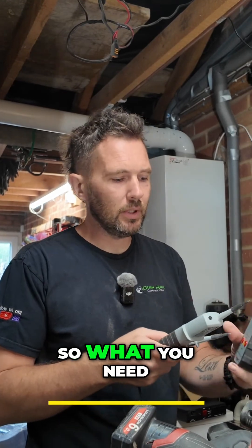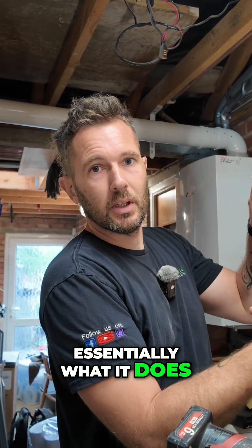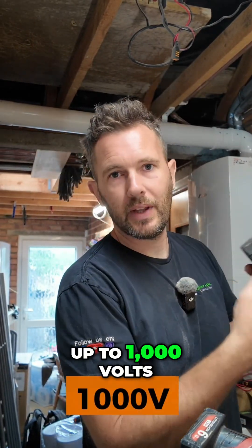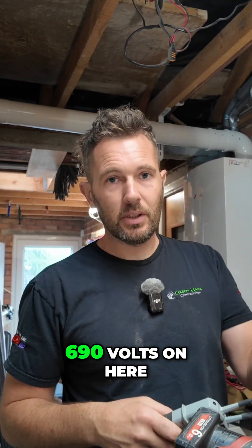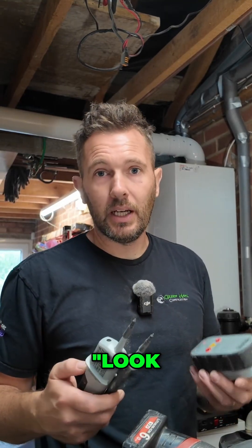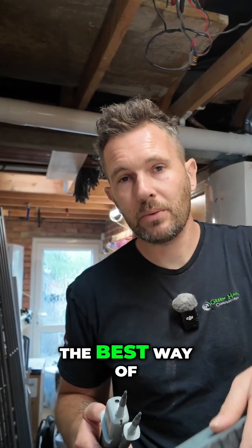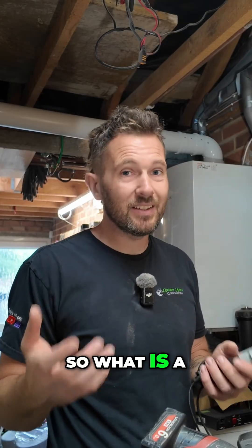What the proving unit does is you stick that in there and it goes through the scale all the way up to 690 volts on this one, to prove that this is working. The assessor actually asked me: fair enough Mike, but how do you know that that's working?